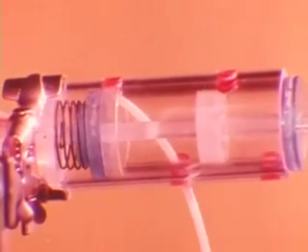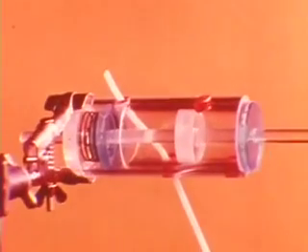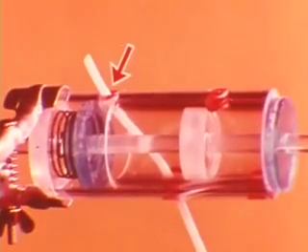Then, if the force generated by oil pressure is stronger than the spring force, the valve will compress the spring and open ports one and two, allowing oil to flow. And if there is no restriction beyond the port, the pressure will drop until the force is balanced against the spring load.